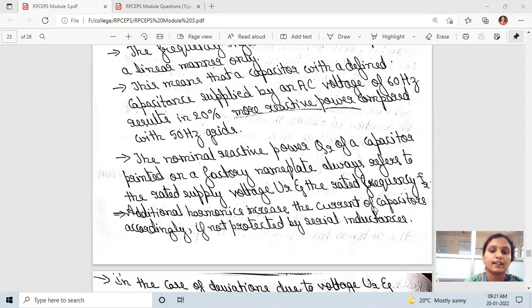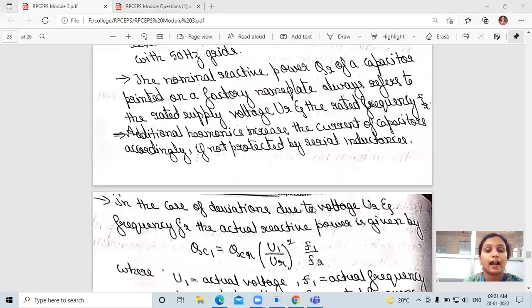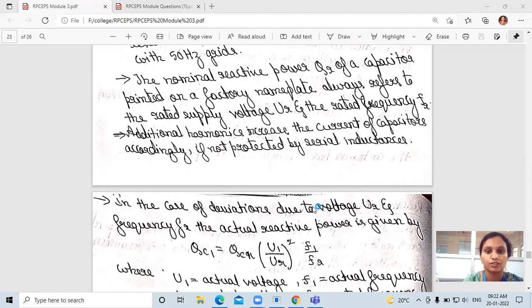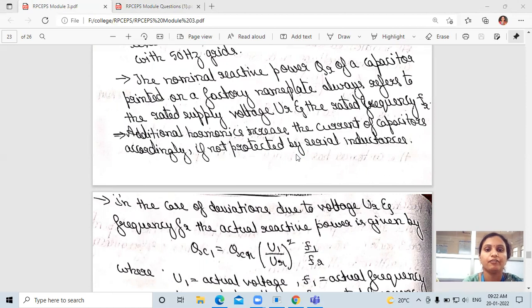Additional harmonics increase the current of capacitors accordingly if not protected by serial inductors. Harmonics in the power system, if you use capacitor banks, must be managed by a controller. If harmonic currents increase, the capacitors should be protected by serial inductance; if not protected, the currents will rise.